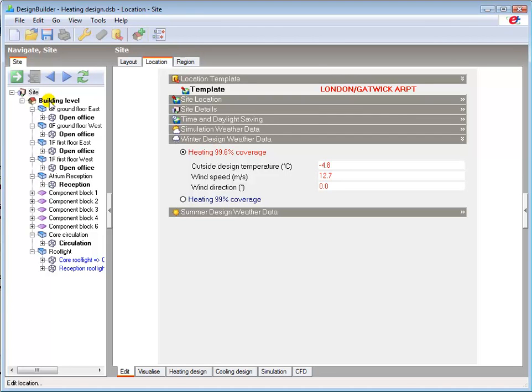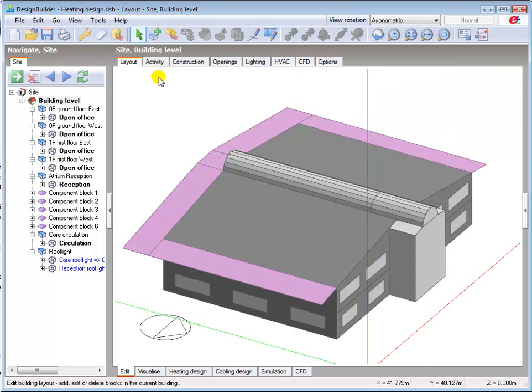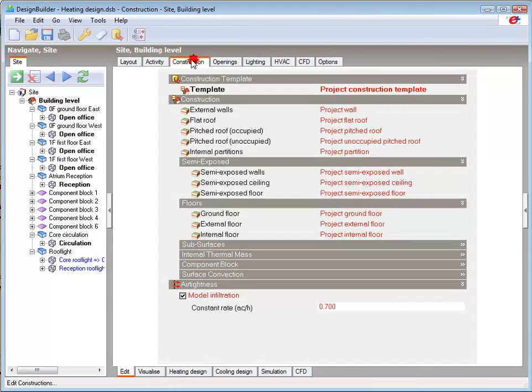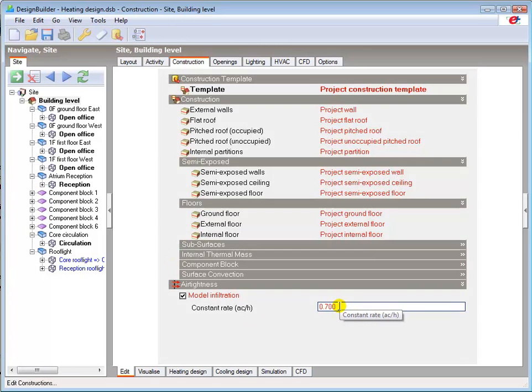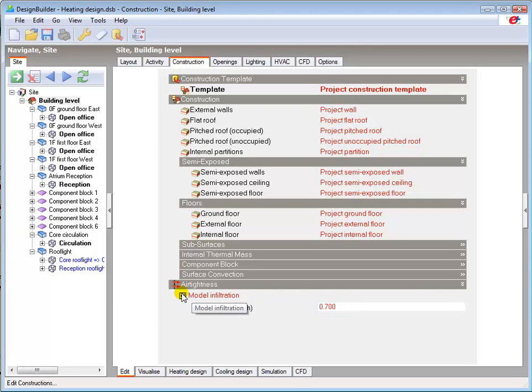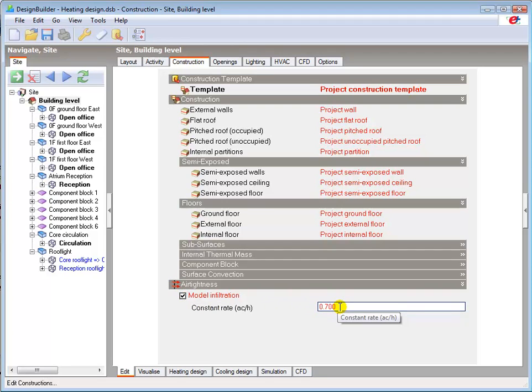You should also check that infiltration is properly defined in the construction tab as this can have a significant impact on the results. You can see here that the model infiltration option is selected set at the default value of 0.7 air changes per hour.